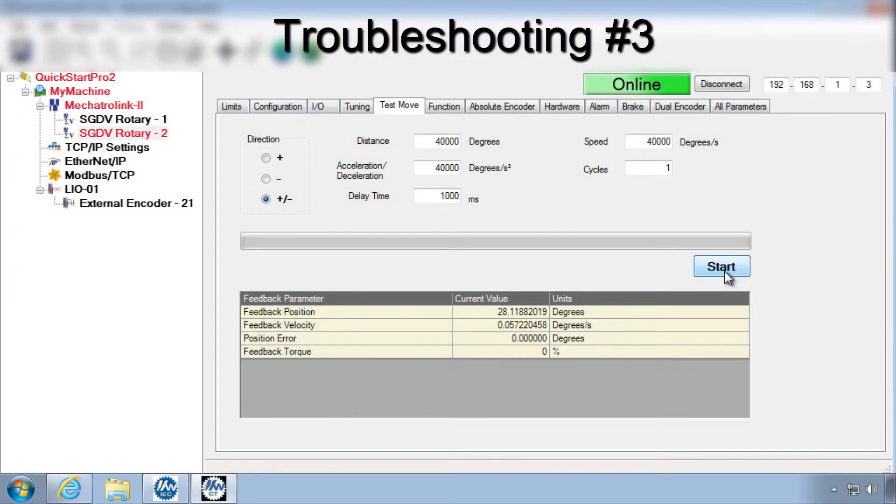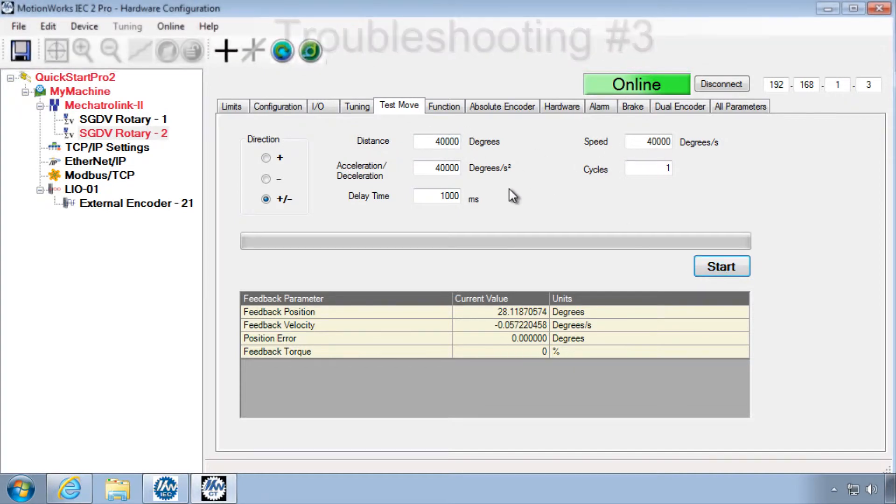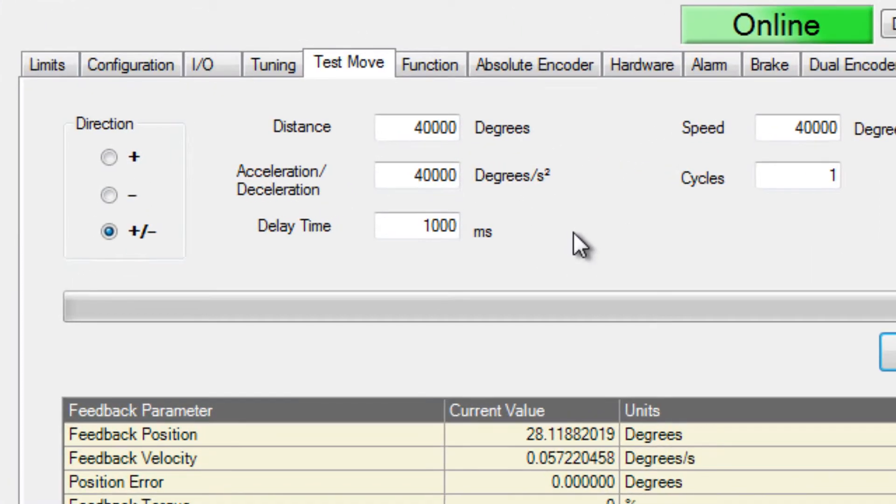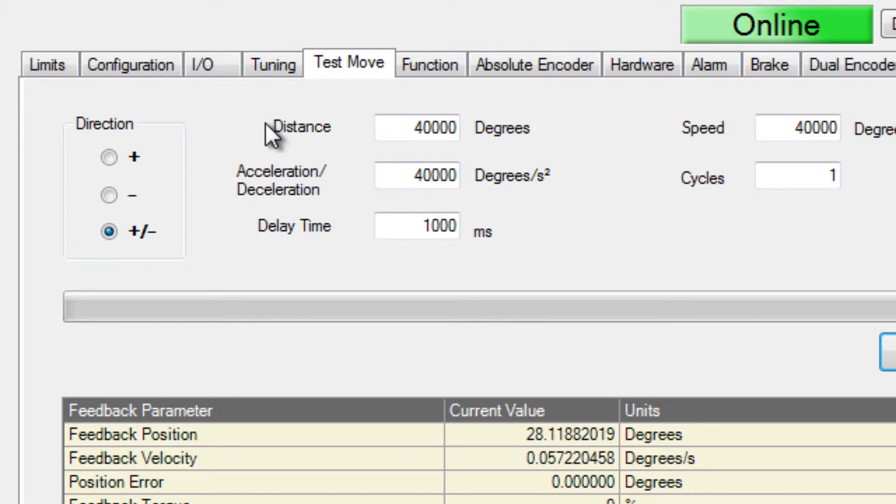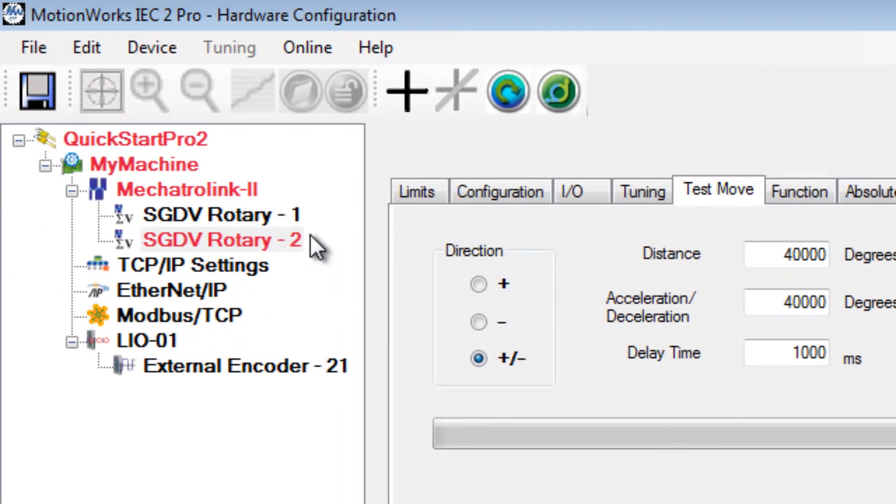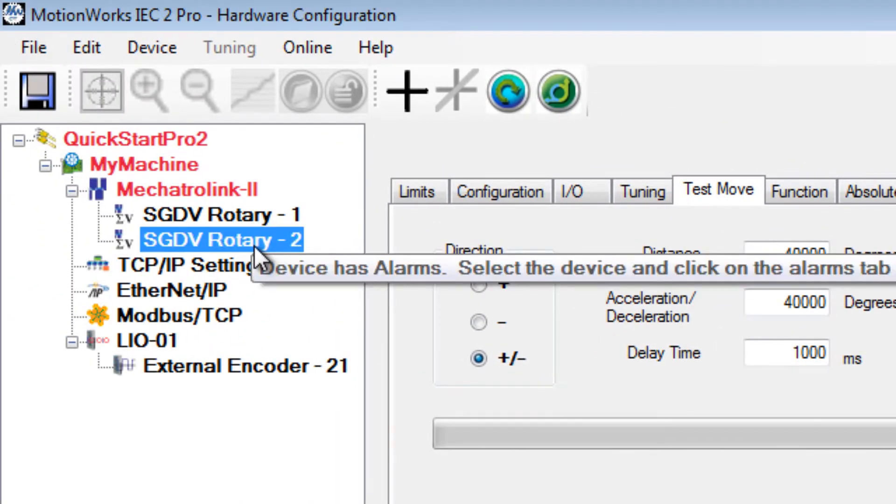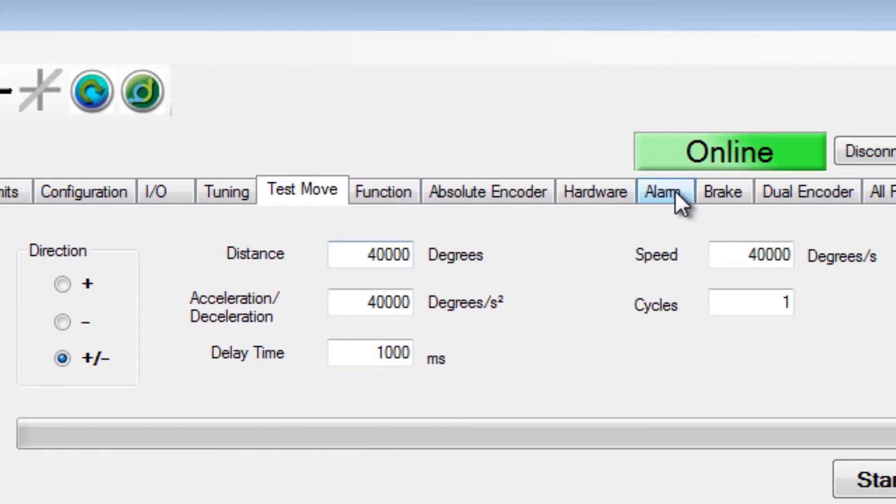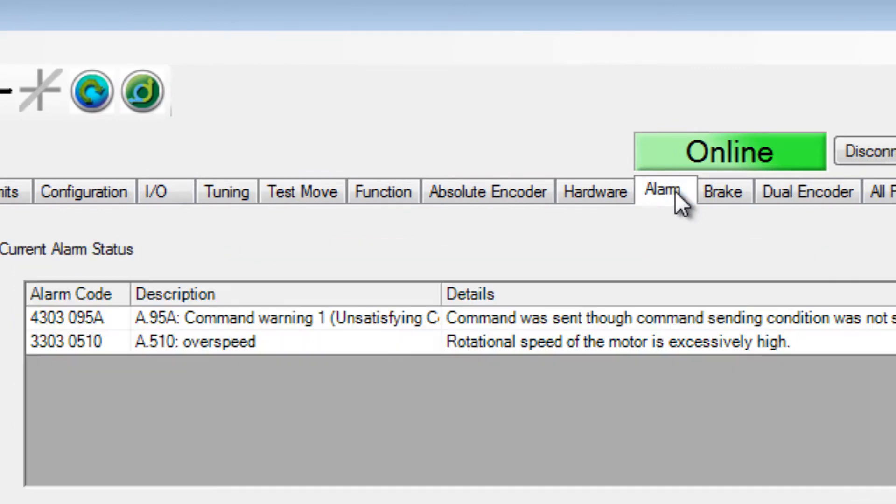If an alarm is generated during the test move, the data you've entered may be out of range or the units configured incorrectly. Over-speed or position error alarms often are the indicators for this problem, and you can see that the alarm axis has a red color. If you click on the alarm tab, you can see this alarm.